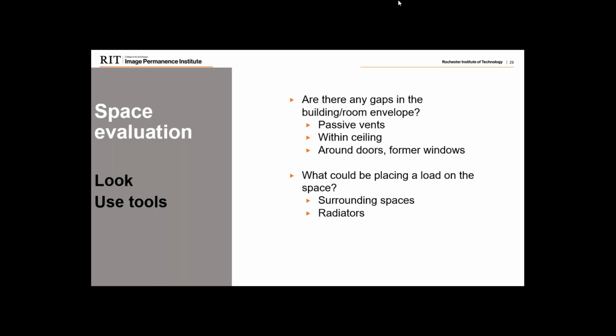And also, identifying things that can place loads on a collection space. Surrounding spaces, if you have a landlocked room that you're trying to condition to, say, 50 degrees, the room is poorly insulated and the halls around it are being conditioned to about 70 degrees, the 50-degree room will struggle to hold that temperature if it's poorly insulated and wind up having a heat load from the surrounding space. So you'll constantly have that heat load being placed on that cooler room without the ability to really fight it off. And the solution there would be to insulate the walls better. Another thing that sometimes places heat loads into a space are radiators, some water source heat or electrical source heat that we have at times seen not turned off in the summertime when it should be off, that cause extra loads within the space.